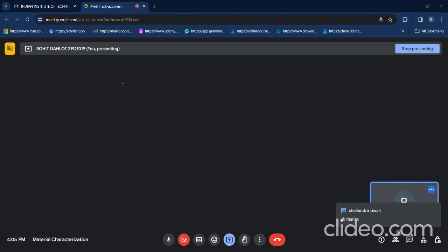And the second one is that the space charge effect is minimum when... I think the space charge was covered in quite a good manner. If anyone would like to write in the comments what it is, it would be good for someone who doesn't know. However, the space charge effect is minimum when your voltage is high and your beam current is low. Then another problem is that an increase in your working distance leads to what effect on spot size and image resolution? Anyone who would like to comment?